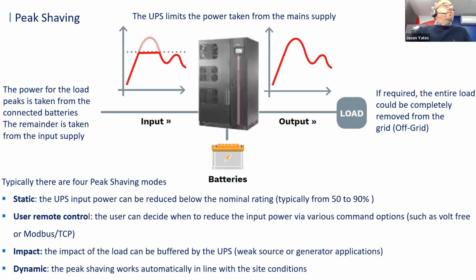Now, for those of you who are not familiar, peak shaving is where we utilize a UPS to limit the power that's being taken from the main supply. The way we do that is if the load on the output of the UPS system increases beyond the set or predefined level, then the UPS system takes a portion of the load from the main supply and the remaining portion of the power from the batteries. So the UPS system can peak shave the load that's applied onto the incomer versus the load that's actually connected to the output of the UPS.